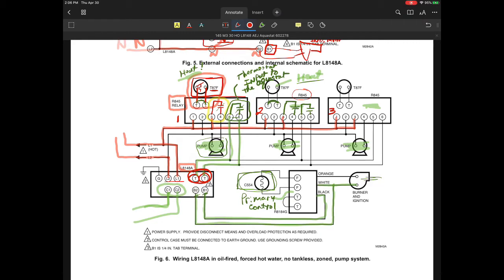If it's zone 1 or zone 2, they're both making a contact closure, and as far as the boiler and the Aquastat are concerned, it's completed the circuit and the system should have a demand. So how do I use this to my advantage? If any one of these burners or boilers or pumps is energized or being told to operate, it's going to take a heating demand, a contact closure, that's going to allow the pump circuits to run, and it's also going to complete the circuit.